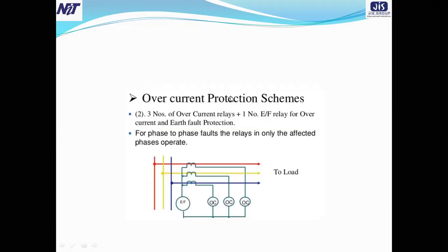Now the overcurrent protection scheme. This is another scheme: three overcurrent relays plus one earth fault relay for overcurrent and earth fault protection. For phase-to-phase faults, the relays in only the affected phases operate. So where the affected phase is, for that area the relay will operate.